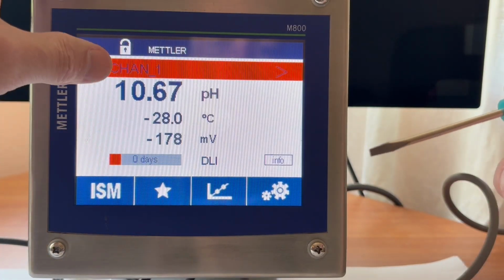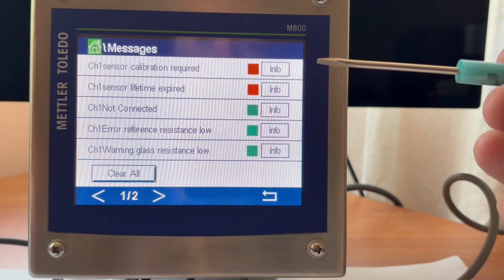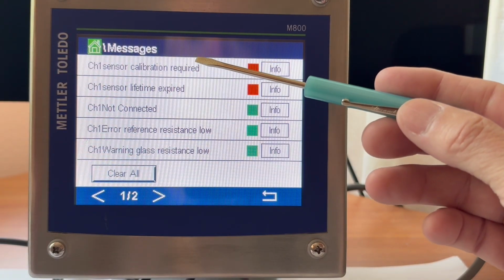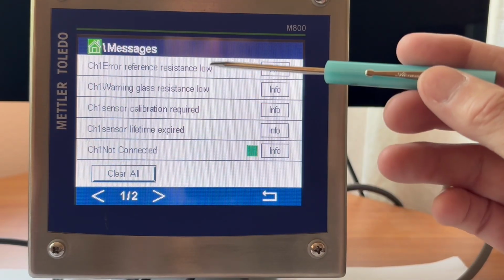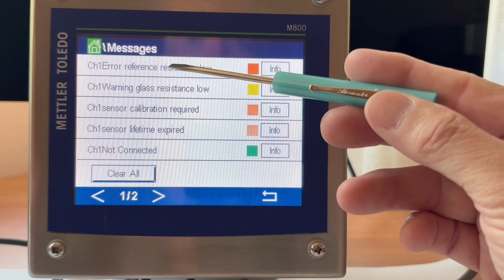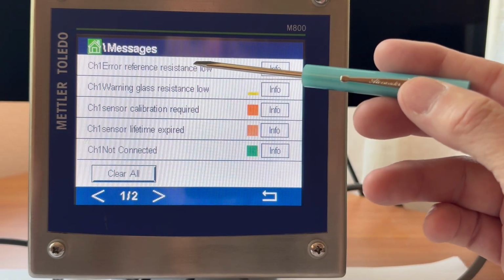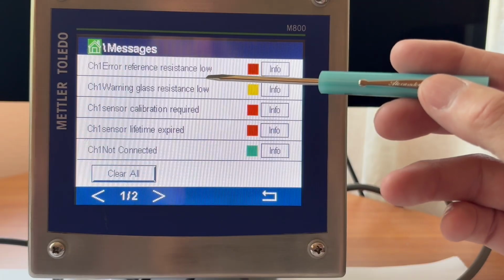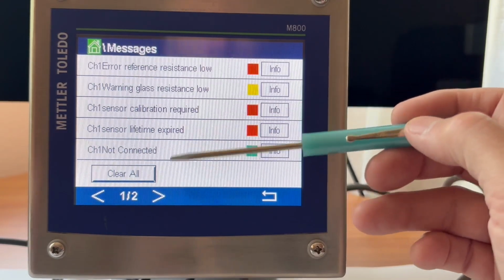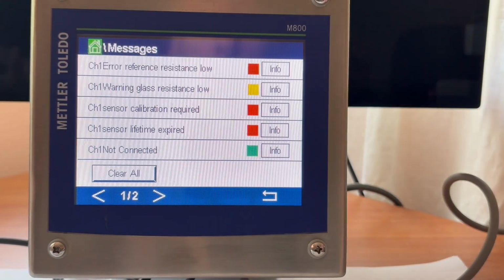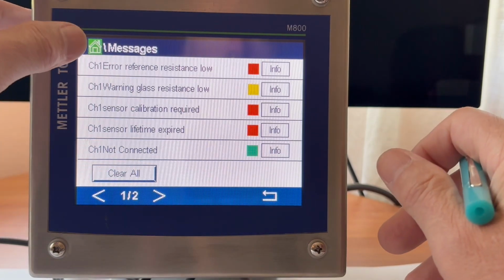But if we look at some of the information, we can go into the red bar. We can see, oh, that sensor needs to be calibrated. And by the way, I've got some other issues. My impedance values on the reference and glass. Reference is shot. Glass is on its way out. Needs to be calibrated, and its life is essentially expired based upon the algorithm.